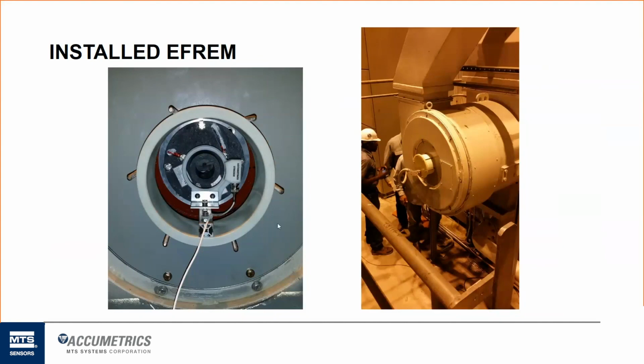The idea is you want to align it slightly axially towards us in this picture, so that way you allow for the rotor growth. When the machine is running for a day or two, it'll reach thermal equilibrium and will actually grow and push that rotor mounted transmitter towards us. So having this setup allows us to adjust that to a range that's going to be the most optimal. Our equipment will operate at a fairly good range. It's typically plus or minus an inch. So even if this stationary component is misaligned up to 1 inch, towards us or further in the Z direction, if you will, that'll still operate.